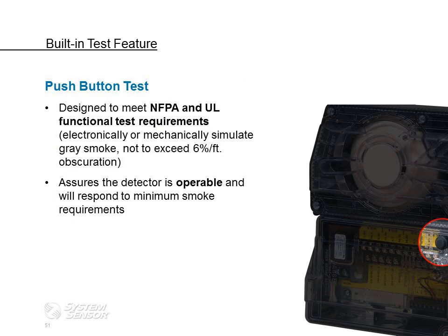The push button test is designed to meet NFPA and UL functional test requirements. What they state is we have to electronically or mechanically simulate gray smoke, not to exceed 6% obscuration. It assures the detector is operable and responds to minimum smoke requirements. This is different from the other products offered in the field, because when you push the test button on other products, what they're actually simulating and testing is the circuitry, that it's wired correctly. Ours actually goes that next step and electronically simulates smoke in the chamber.